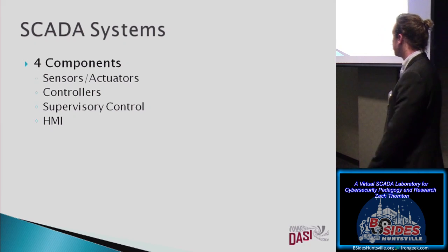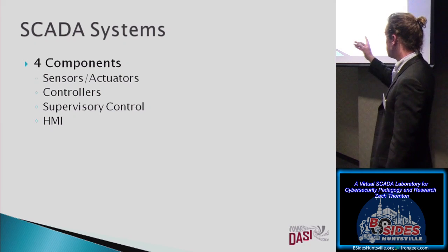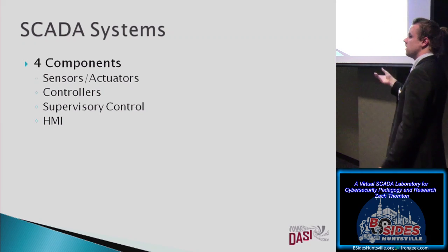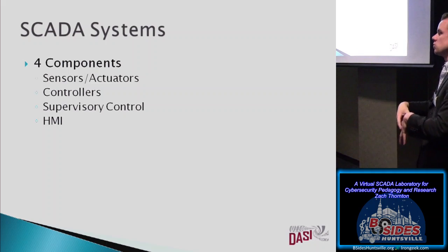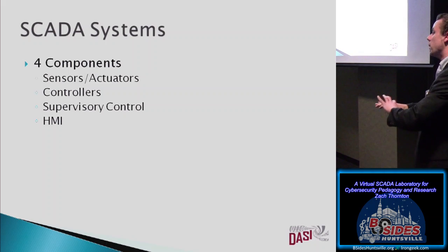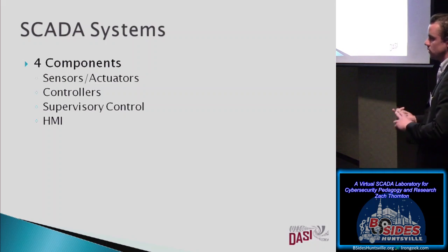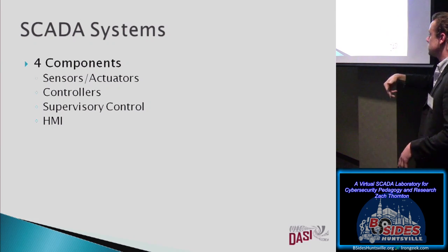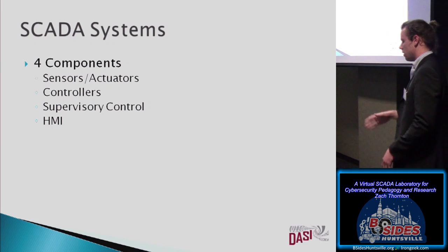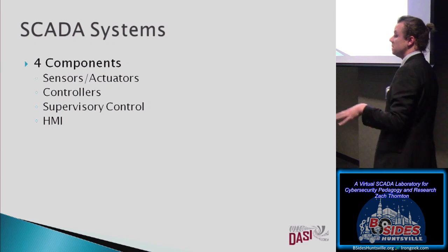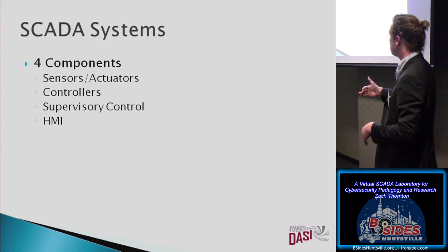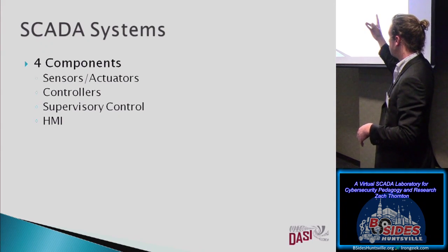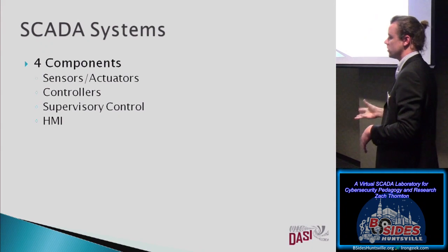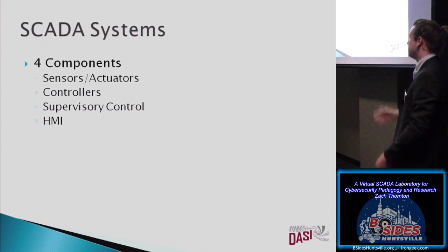So sensors and actuators - controllers are usually the targets for cyber attacks, since sensors feed data into the controller. Sometimes it's just a 16-bit microprocessor, but it's encapsulated. It has an analog to digital converter, digital to analog. So that's what's doing the controls. The sensor reports data, and the control says, okay, pressure is at this point, now I need to affect something. So controllers make the decision on how to open or close a valve, how much to open or close it, turn on and off a pump, that kind of thing.